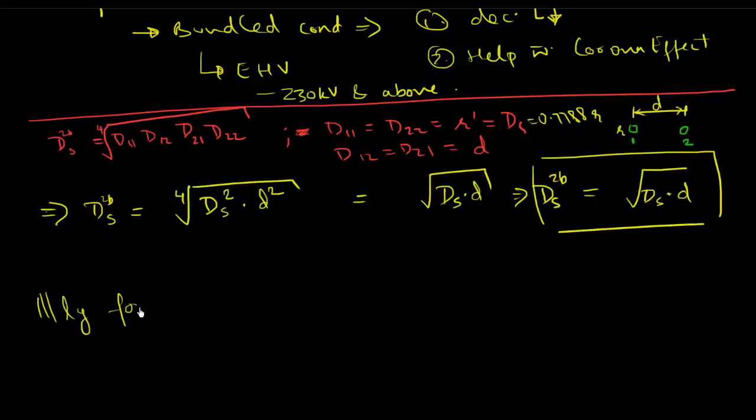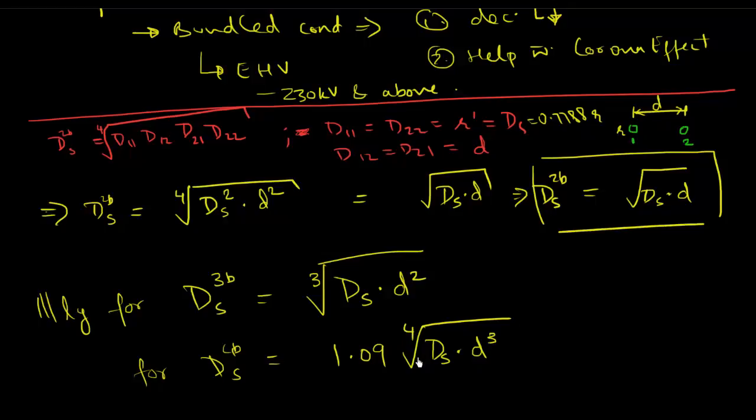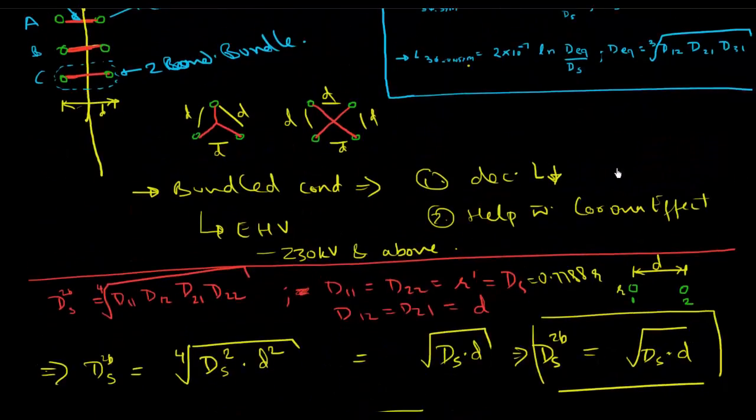Similarly, for a three-bundle conductor, we'll get the value is equal to the cube root of ds times d squared. And for four bundles, we would have ds^4b is equal to 1.09 times the fourth root of ds times d cubed. I want you to try and use this formulation and derive these equations. If you can't, let me know and I'll solve them out for you, but it's relatively straightforward once you plug in all the values.